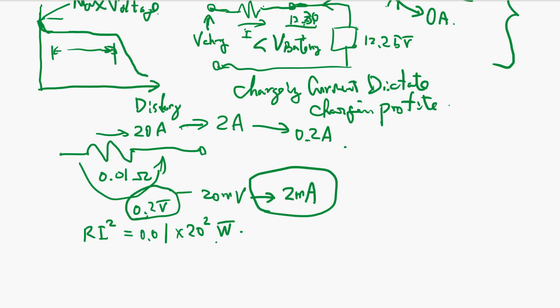When it goes down to 2 amps, we're talking about 20 millivolts. And when it drops to 0.2 amps, that's 2 millivolts. So we have to detect extremely low voltage, but the AD converter cannot handle this - the reliable range is about 5 millivolts.